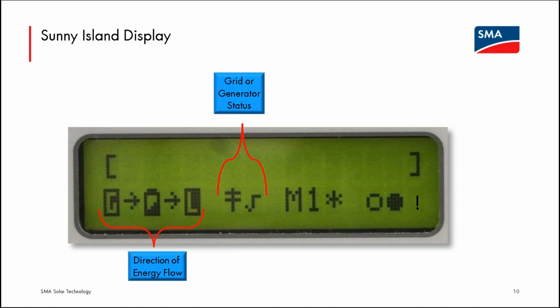It's possible for the directions of those arrows to reverse. If there is PV or a small wind inverter on the protected loads panel, if there's excess power, the Sunny Island is set to allow that to backfeed past it back to the grid. That can be disabled so that there will be no grid backfeed. And when the input on the AC2 terminals is the generator, the Sunny Island will change to not allow any backfeed to the generator, no matter what the grid settings are. So the Sunny Island is very smart and will manage its power sources very efficiently.